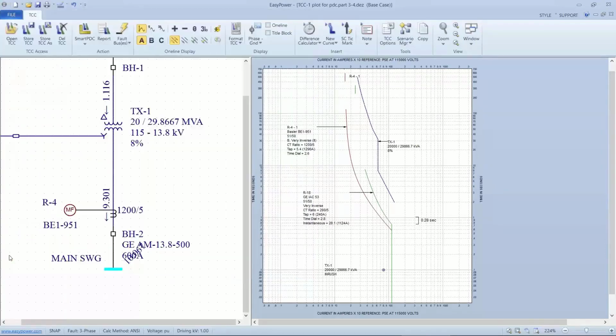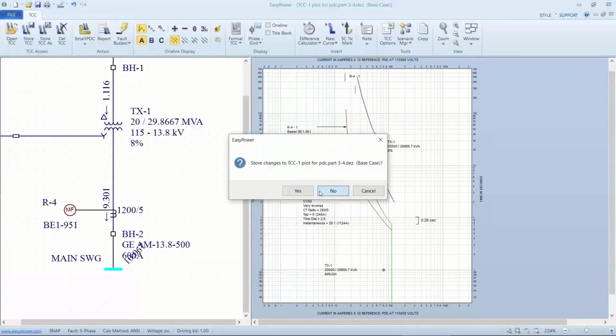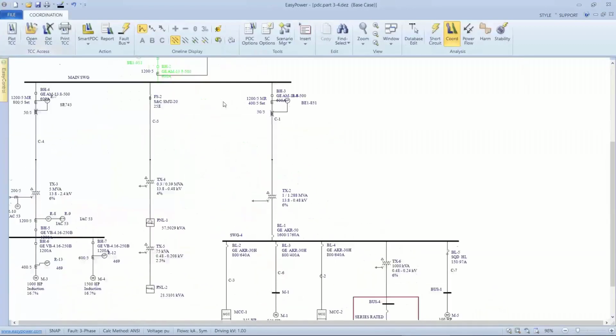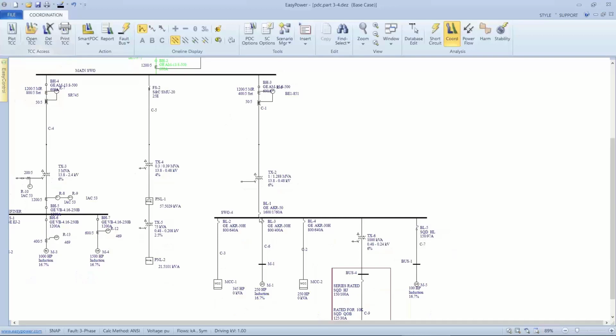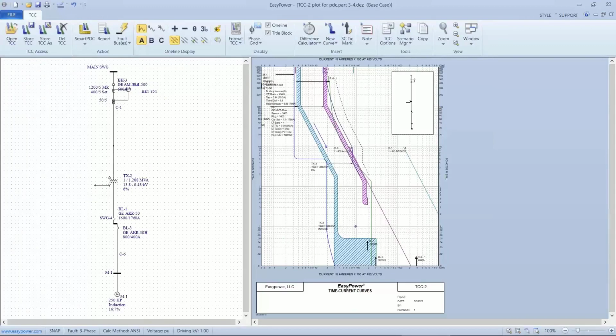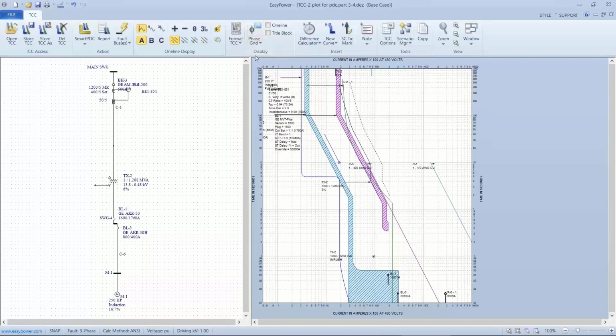So I would save this plot, which I'm not going to do now, but the dial settings are saved. Now we're going to coordinate this leg right here. So again, we haven't overlapped between those settings and these top three breakers, but that's something I would do next. For now, let's talk about this particular leg because we're going to start at the motor. All right. The motor is the violet curve.